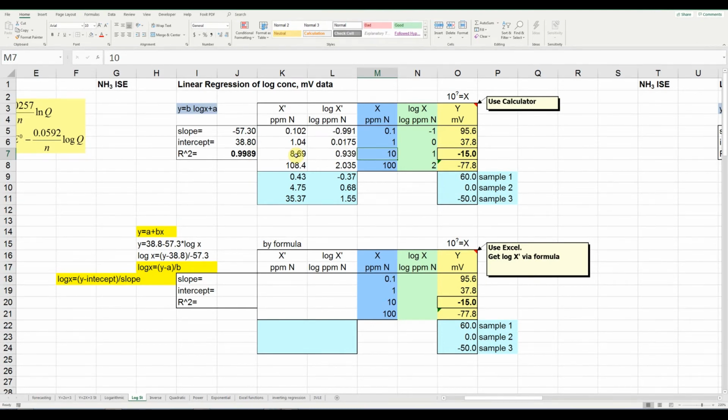If you took your data home and looked at this, you have no option but to discard the data. And then you're down to 3 data points maximum, and that's not good. But if you'd run it right at the time you did it, you could have caught the fact that your partner messed up here, and you could have made a new standard or run it again and checked. On the 100 ppm standard, we're measuring 108, still not great, that's 8% too high.